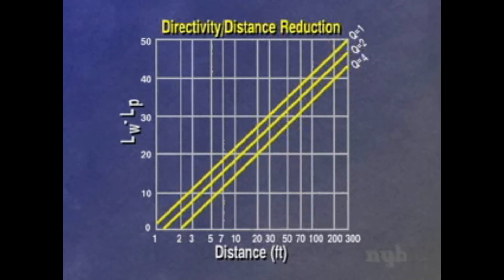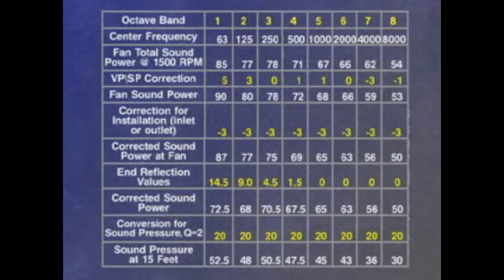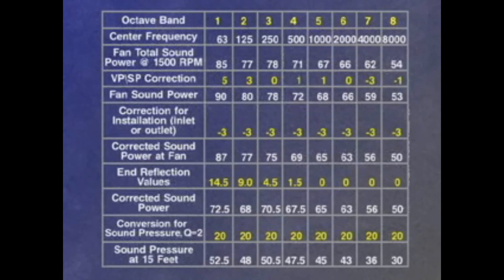Combining directivity factors and distance yields a graph. The further the distance and the fewer the reflecting surfaces, the larger the decibel reduction. Let's assume a floor-mounted fan in a large area, 15 feet from the listening location. This gives us the estimated sound pressure for this application.